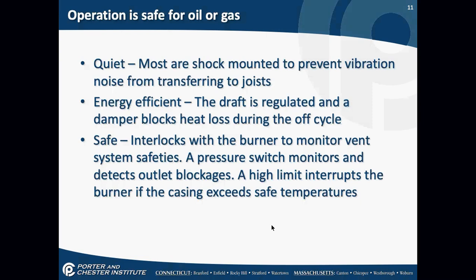Operation of the power venters, we use them on both gas and oil equipment. Okay, they're quiet. Most of these are mounted on shocks, little springs, little pieces of rubber to prevent vibration transferring to the floor joists. They're energy efficient. We have much more control over the draft, and a damper closes and blocks heat loss during the off cycle. They are safe. They interlock with the burner to monitor vent systems. Okay, a pressure switch monitors and detects outlet blockages.